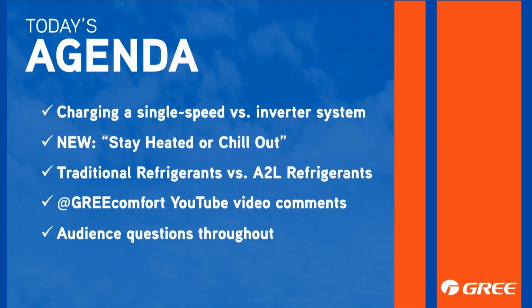Whether that's a 2-speed compressor or some kind of weird inverter hybrid type of compressor that I've recently seen, they're adding more components, moving components, operating components within a hermetically sealed chamber. I'd rather replace the board than have to swap out a whole compressor every single time. That also makes compressors a lot more expensive too. Right. Especially if you take it one step further and compare it to a 2-stage compressor. The top of that scroll plate's got to turn. I can't think of the name of it off the top of my head, but yeah, it's another mechanical part that could fail, in a scroll compressor.